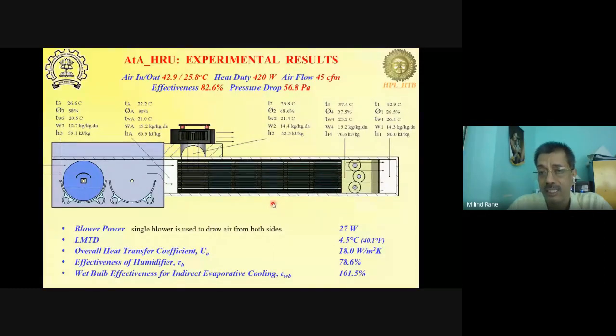And as you can see here, the plastic heat exchanger enables us to reduce the weight and cost. Typically, the cost of a plastic heat exchanger will be almost 8 to 9 times lower compared to a comparable copper-based heat exchanger, or if it is aluminum, it will be at least 3 to 4 times cheaper than aluminum, because the density of polypropylene is around 0.9, while that of aluminum is around 2.7 kg per liter. So you can see that the weight itself becomes one third, and then the cost per kg of the plastic is obviously going to be lower than the cost per kg of aluminum by almost half. So you have about 5 to 6 times difference in the cost per unit surface area. And also, it is easier to produce thinner sheets of plastic than aluminum.